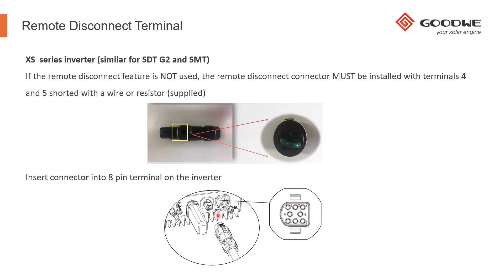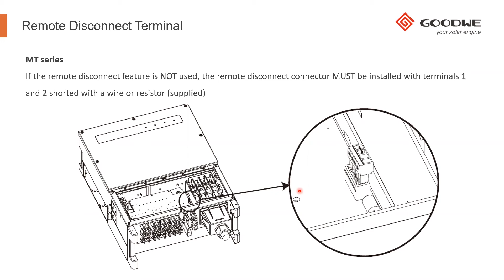For the MT series, the remote disconnect terminal is slightly different. It's actually a green 4-pin terminal, which you can see here on the right-hand side. You can see the short circuit again across pin 1 and 2, and this must be inserted. Otherwise, the inverter again will go into waiting mode. So just be conscious of the fact that you need to have this remote terminal connected in case you're not using the remote shutdown feature.